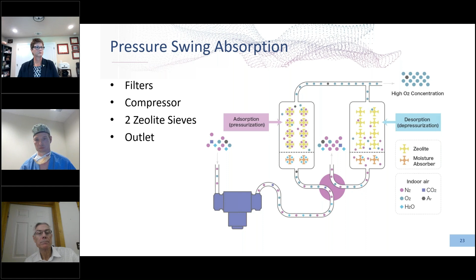This is actually my generator. So this is taken in Djibouti. You'll notice the third picture from the left is the compressor. It is outside because it's incredibly loud. So you never have it inside patient care spaces. We generally locate that outside, and that gives it plenty of flow to air. Then the compressor feeds into the generator. That's the leftmost picture there. And that's the one that actually does the swing absorption and actually generates the oxygen.